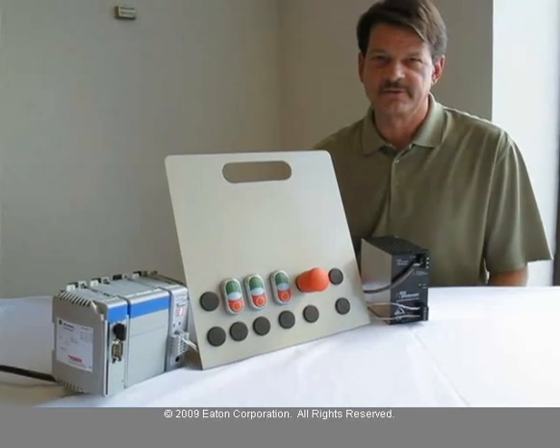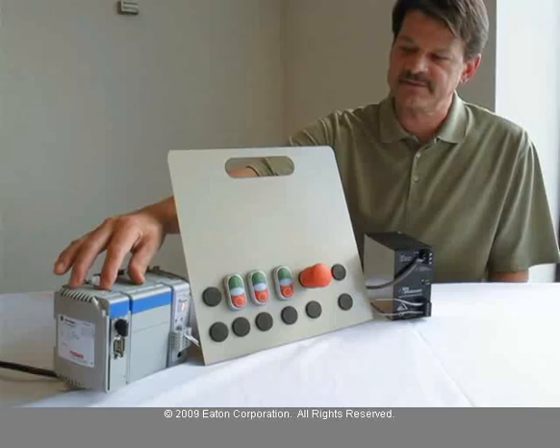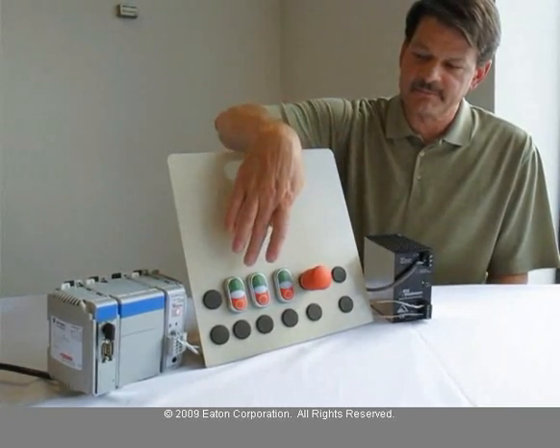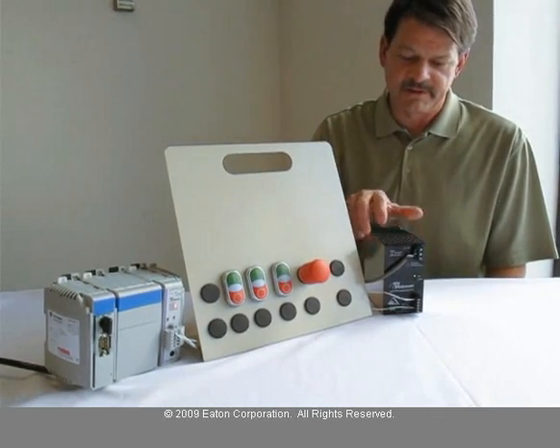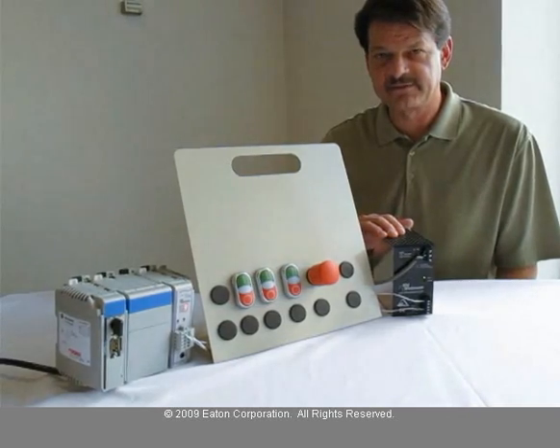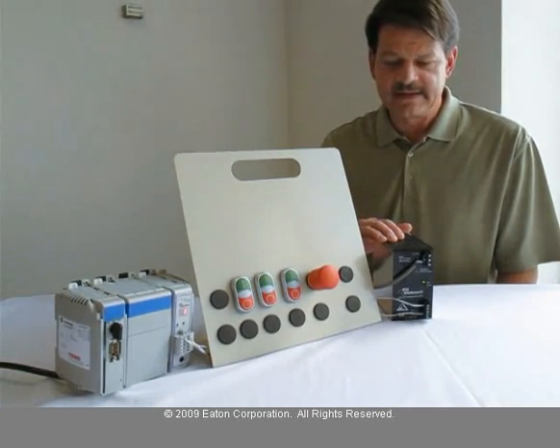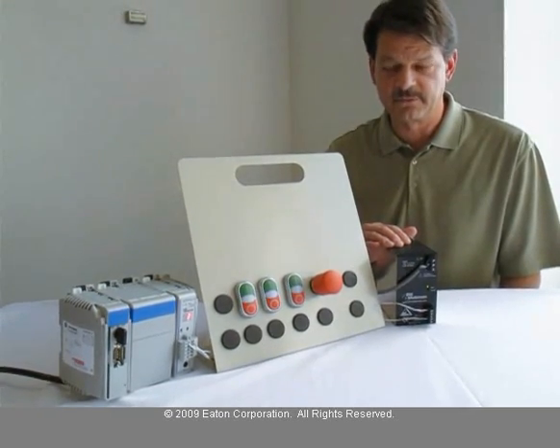I'd also like to show you a complete AS-i system, an example. Here's a PLC with an AS-i scanner master, pulling these four M22 devices. Also, we have a power supply — an AS-i power supply on the network. It's a special power supply that supplies 30 volts DC to the network devices, and decouples the communications from the power on those two wires.